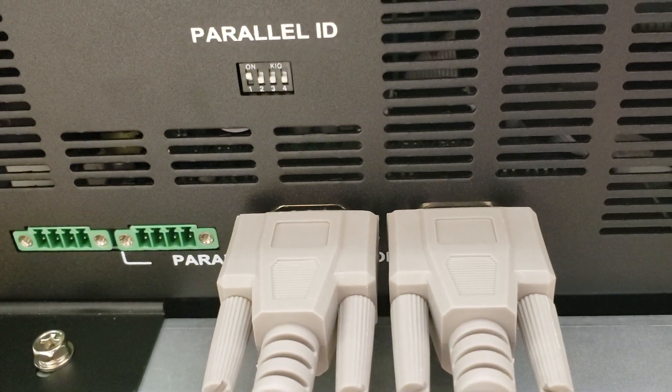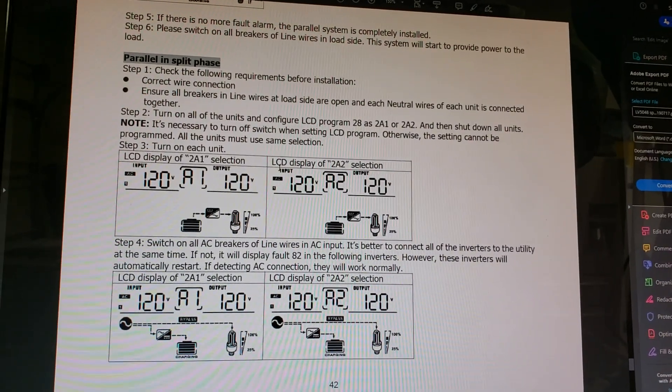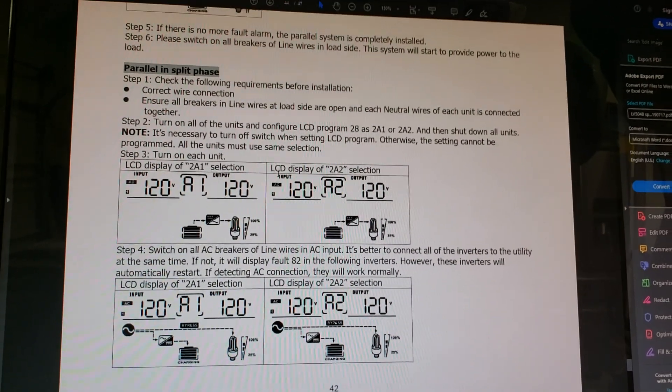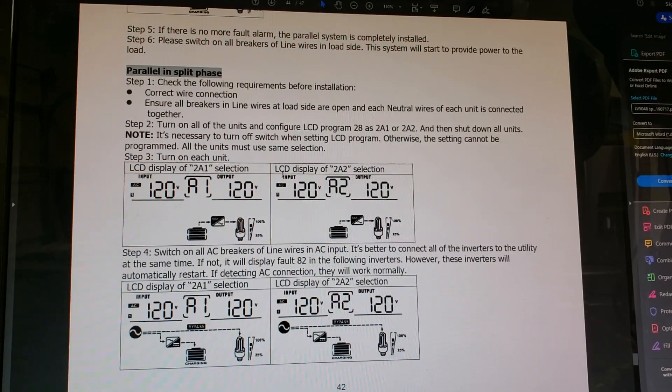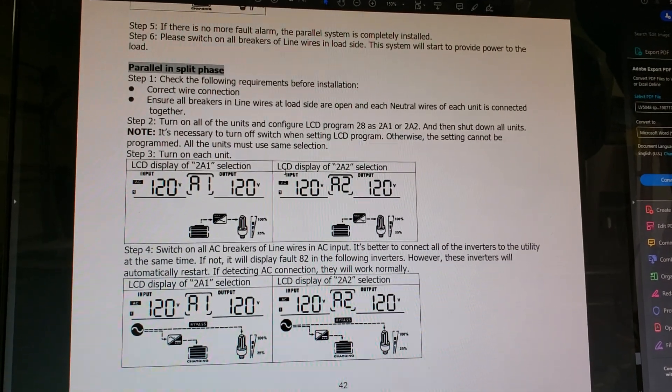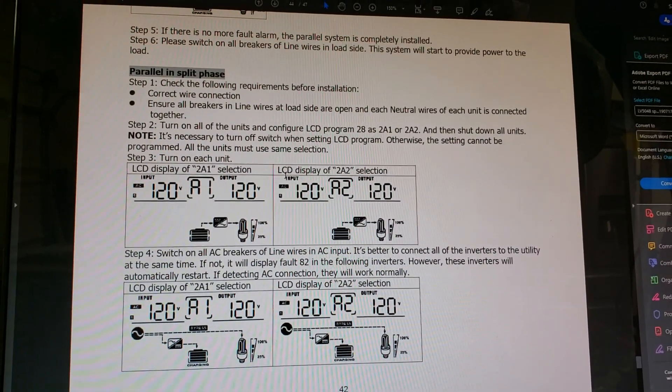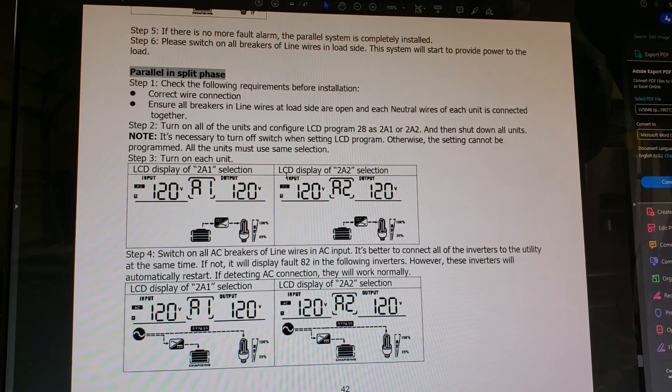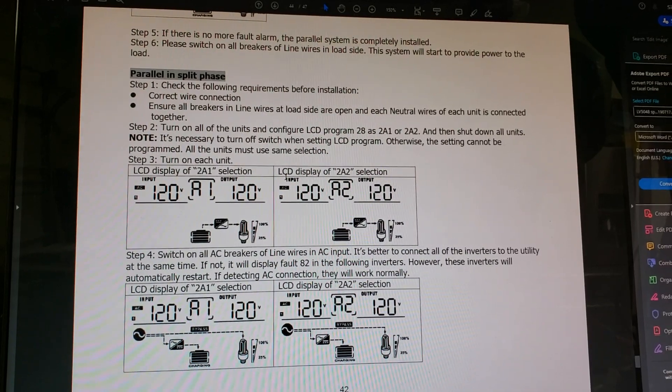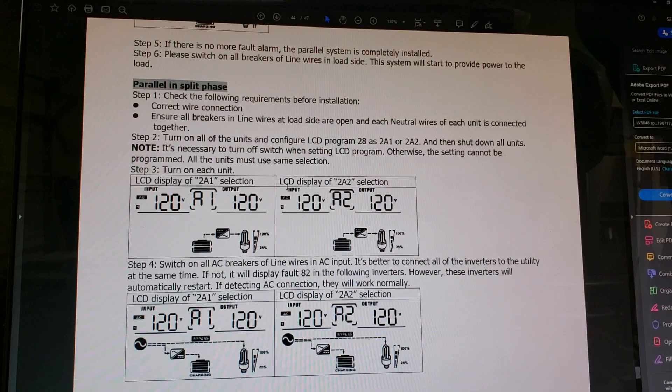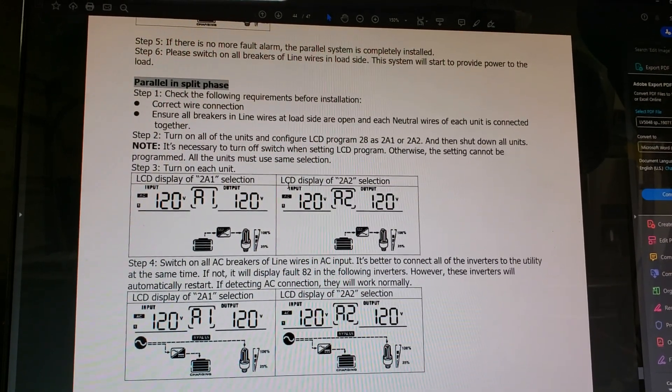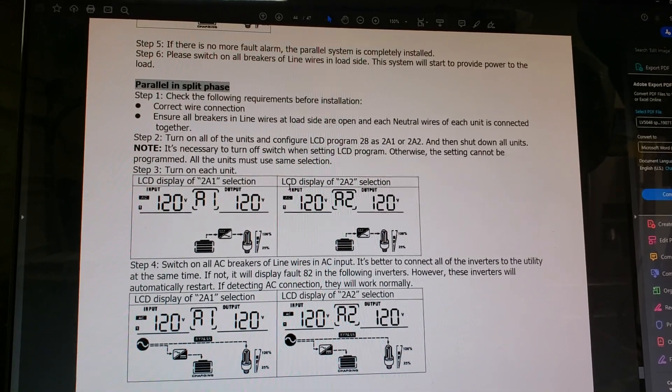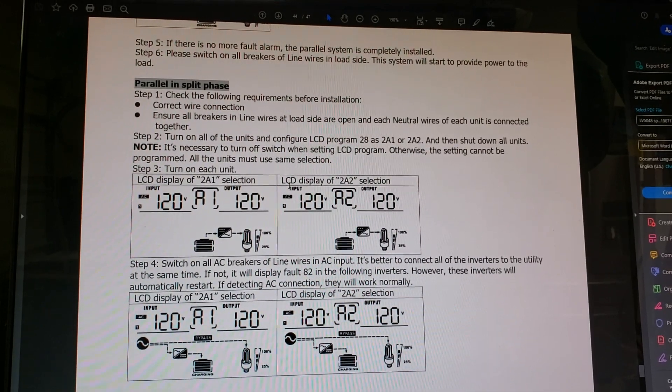Now that we have both units physically connected together, parallel ID switches set in the proper mode, and the communication cables hooked up properly, we do have to set up menu items on the inverters themselves properly. Otherwise you can cause damage or the inverter will most likely give you an error code. The way I did it might not be exactly as it says in the book, but I turned on one unit and went into the programming menu to program number 28.